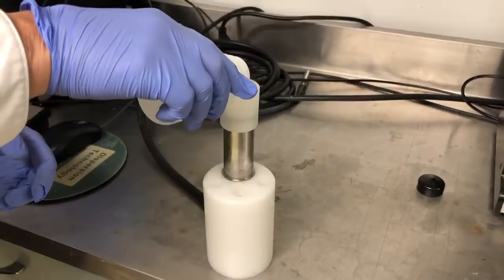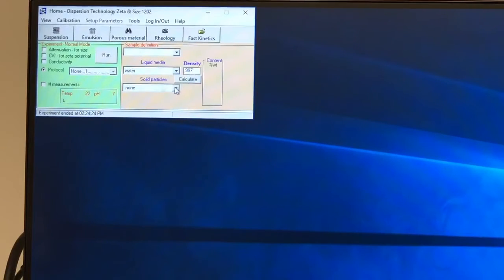We first load the sample cup with our solution. We then define the experiment we plan to run. Since we are going to make a zeta potential measurement, we click the checkbox labeled CVI for zeta potential. We then move to the sample definition section and define our sample. We set the liquid media to water, the dispersed phase to silica ludox, and the concentration to 10 weight%. Lastly, we click the large Run button to begin the experiment.